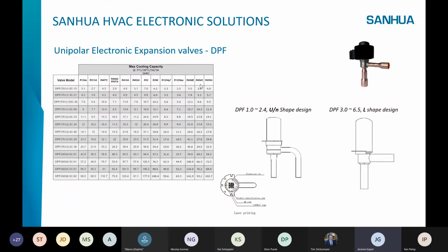We have different refrigerants and different models for the capacity. For R32, the maximum cooling capacity for these conditions is 7 kilowatt for the small valve till 180 kilowatt for the big valve. We have different shape designs. The small valves are designed in a U shape or N shape, it depends on the position of the valve. And for the big ones, from 3.0 to 6.5, we have only L shape. So the inlet of the liquid is on the horizontal tube, and the outlet is on the vertical tube.